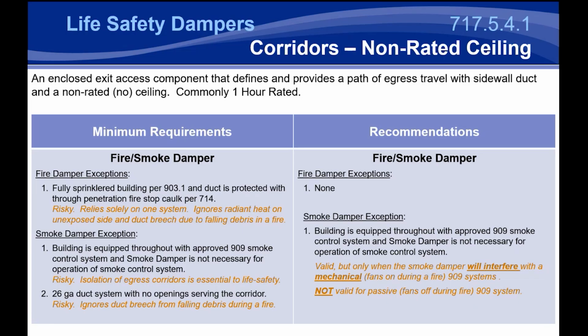The exception I see used the most is if you've got 26 gauge ducts with a system that has no openings serving a corridor. I see this used quite a bit. It is a bit risky due to the duct breach from falling debris, but I do see engineers use this quite a bit to potentially reduce the number of fire smoke dampers throughout the building. So it is an exception that's used quite a bit throughout the industry. It is a little bit risky, but it is something that is widely used.